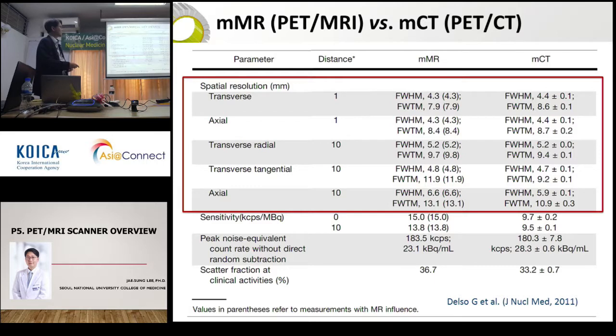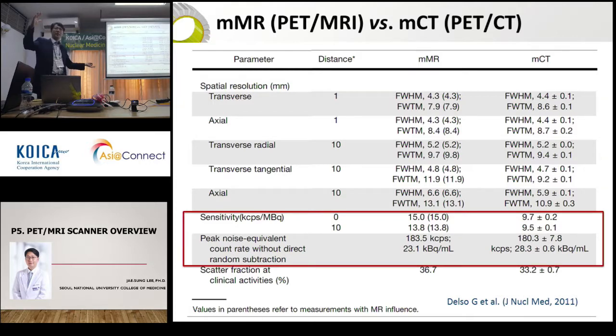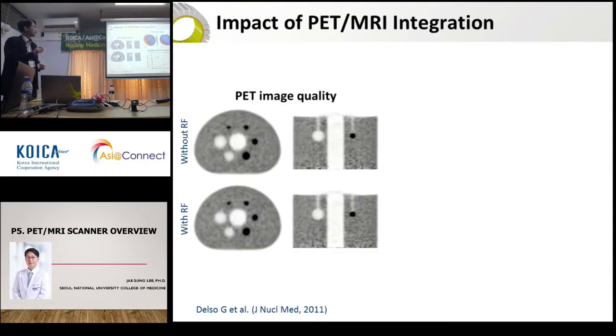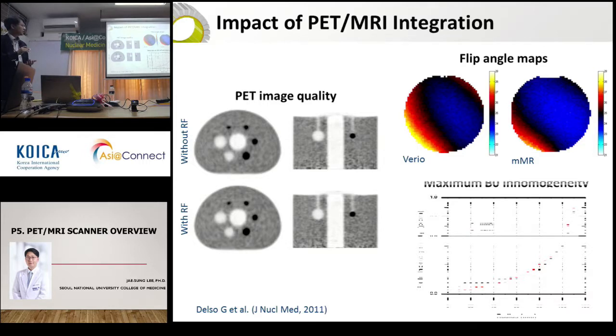If we look at the specification of their PET MRI system, they use the same LSO crystal with the same size as their mCT PET scanner. But as I told you, the energy and time resolution of the detectors in the PET system is worse than the PMT based systems. But they can achieve better or equivalent spatial resolution, because they have a smaller bore. And the sensitivity should be higher because the bore size is smaller than their conventional systems.